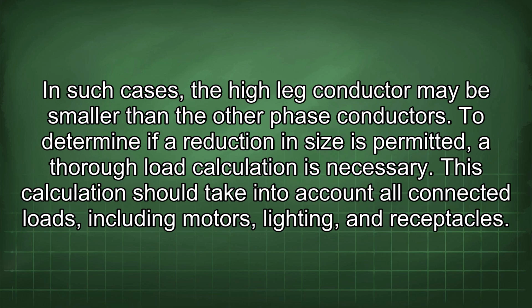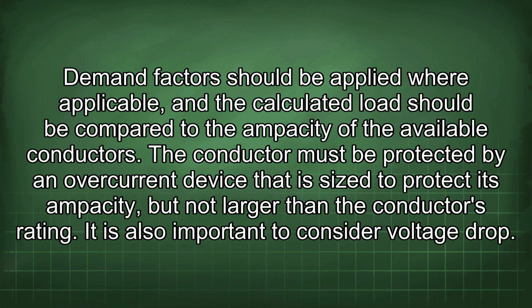To determine if a reduction in size is permitted, a thorough load calculation is necessary. This calculation should take into account all connected loads, including motors, lighting, and receptacles. Demand factors should be applied where applicable, and the calculated load should be compared to the ampacity of the available conductors. The conductor must be protected by an overcurrent device that is sized to protect its ampacity, but not larger than the conductor's rating. It is also important to consider voltage drop.